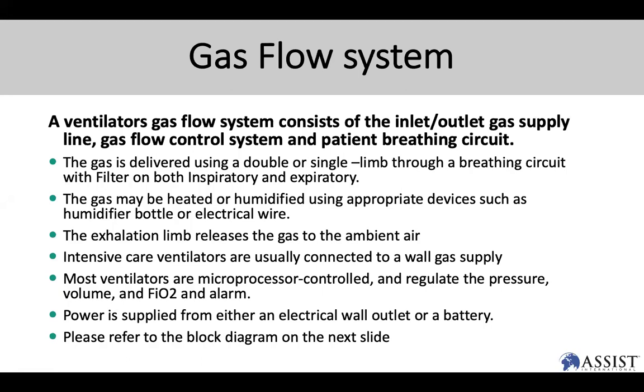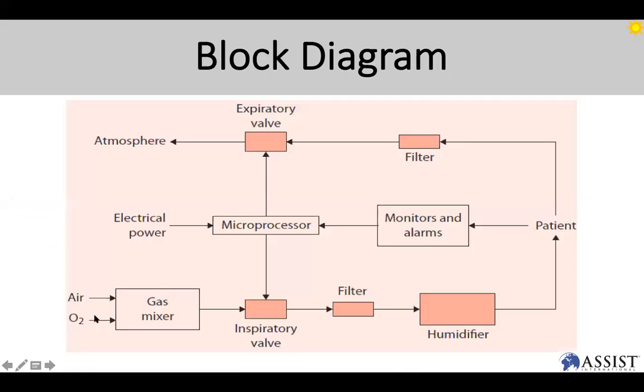Okay, the block diagram. So basically, you got air and oxygen input from, it can be centralized or cylinder line or something like that. Depends on the hospital setting. So when you talk about gas line, you normally got gas mixer, all that. So that's the first block diagram, and you got expiratory valve, inspiratory valve, then your monitoring alarm, microprocessor, power input with the battery, all that. And you got humidifier, patient circuit, filters, and on the expiratory valve, that's an atmosphere output. So basically what happens is, your breath out will go back to the atmosphere. So that's the block diagram normally you see in the ventilator.